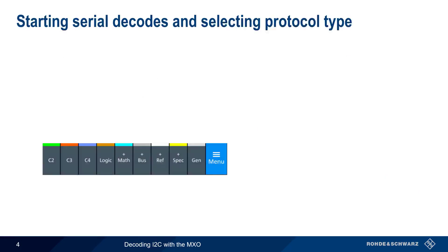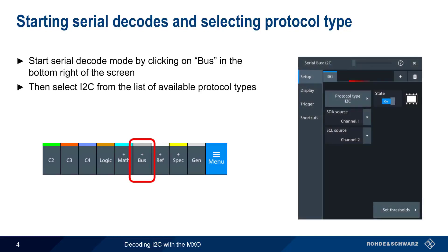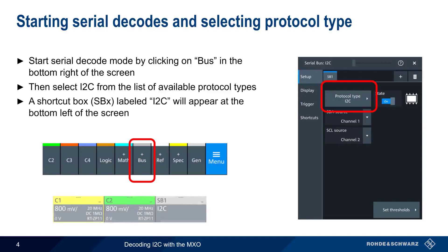The first step in decoding I2C data with the MXO is to select BUS from the list of items in the bottom right corner of the screen. Then select I2C from the list of available protocol types. This will also create a small box labeled I2C in the signal bar near the bottom left corner of the screen, which can be used as a shortcut for configuring I2C parameters.